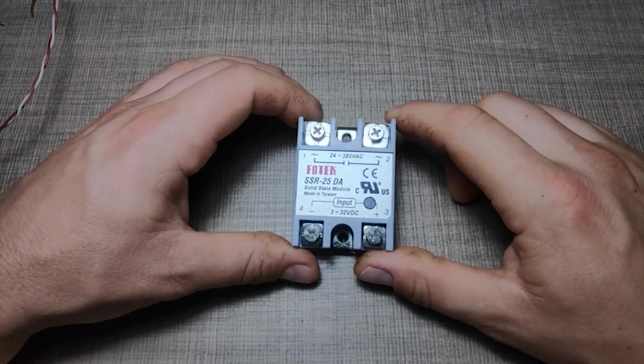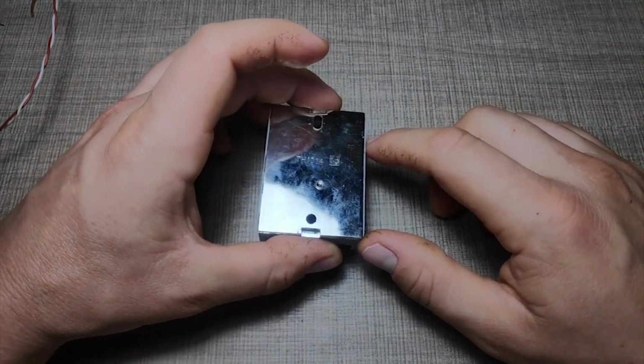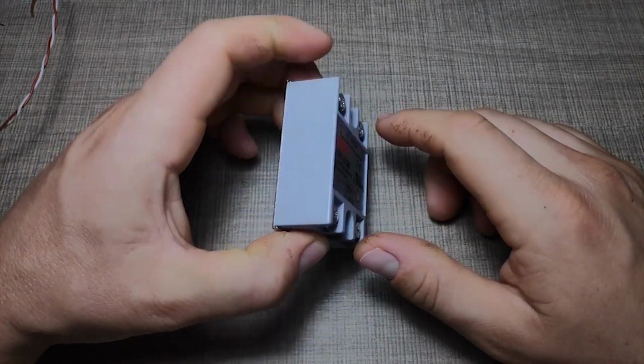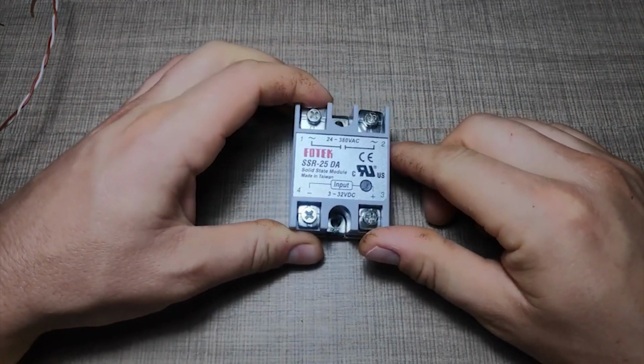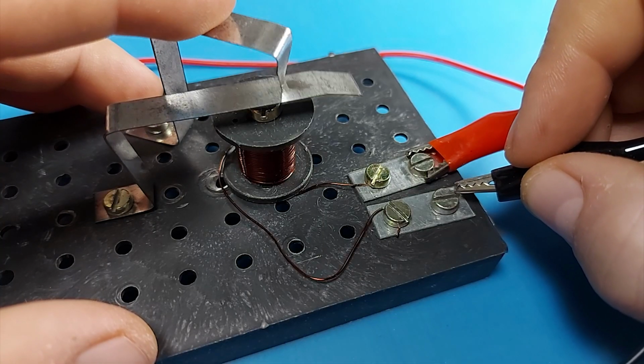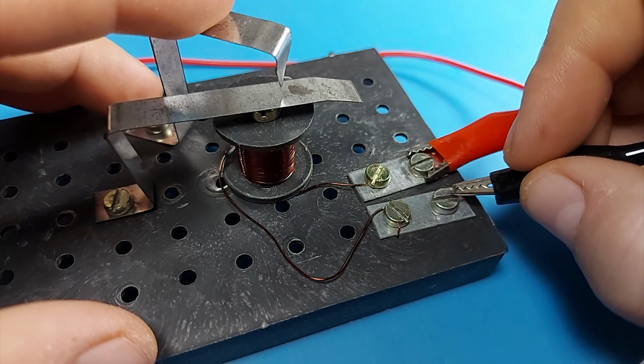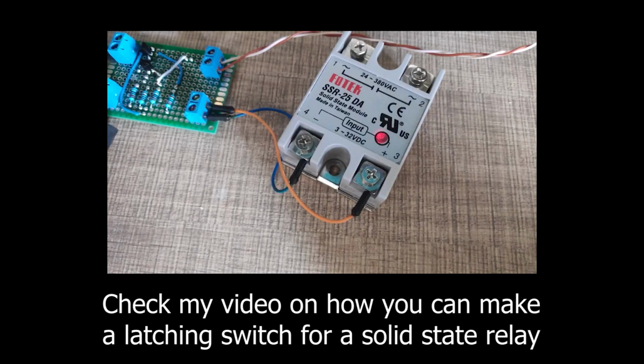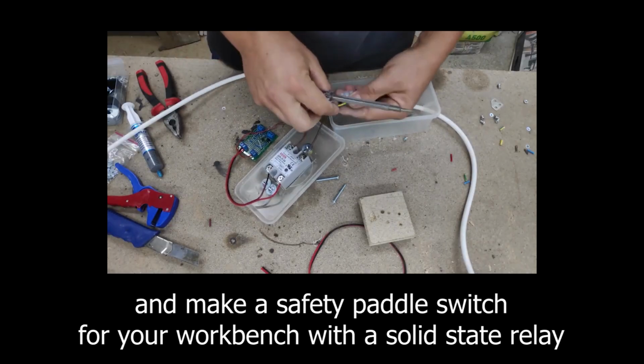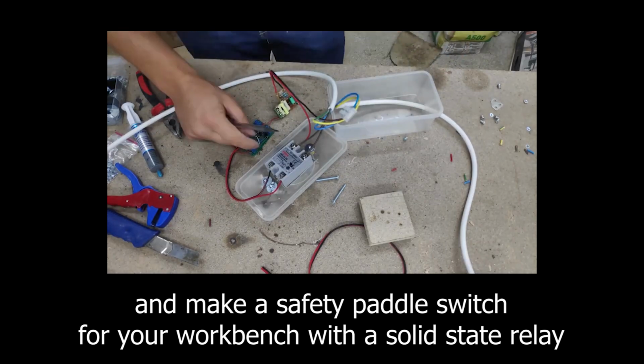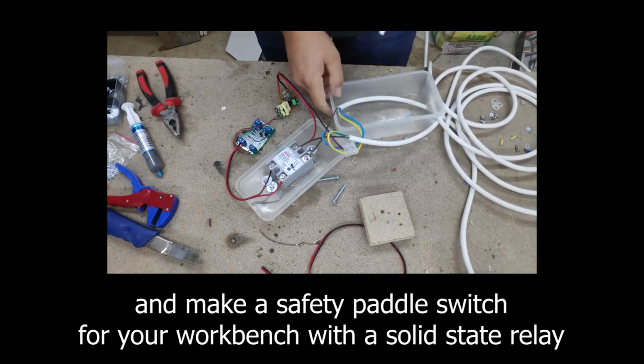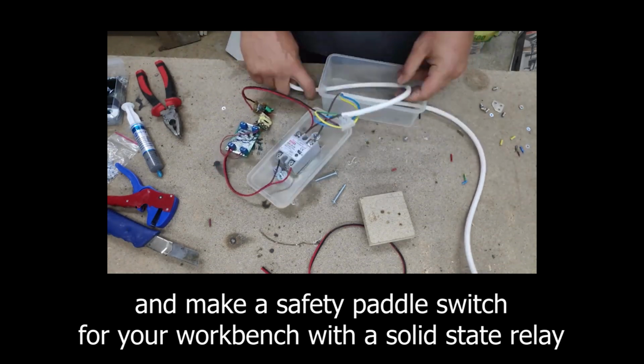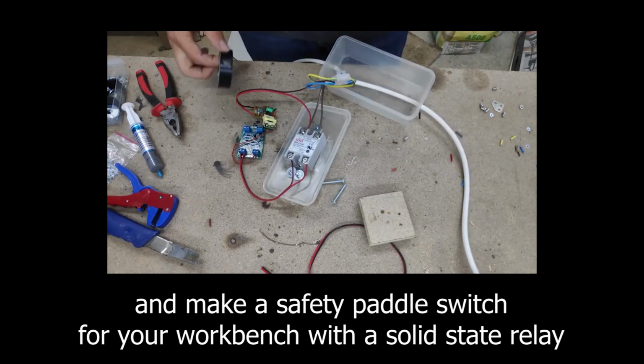Other than the mechanical relays that we saw so far, there is also another type of relay called a solid-state relay. As the name implies, this type of relay does not have any moving parts and it does the switching through a thyristor. Since there are no moving parts, these relays can in theory last longer than their mechanical counterparts, but they come with two caveats. When they fail, they typically fail in a way that they stay on with active load and they are much more sensitive to electrical noise. So, keep this in mind when choosing between both.